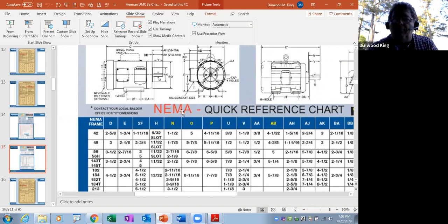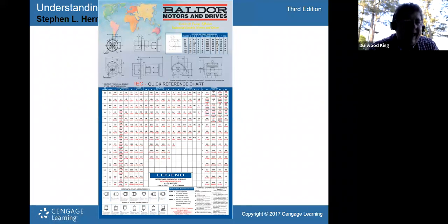But if you got motors that come from overseas, let's back up and look. Let me go back to full screen. Now, if I back up one, it says IEC. So the IEC is the International Electrotechnical Commission, and they're based out of, is it the Netherlands or somewhere over there in Europe? It's European. I forget what it is, and it may be even Belgium. It may be Brussels or somewhere over there, but it's Europe. So the IEC are metric. They're metric designations. So any equipment you get from overseas is going to have IEC rated motors, and the frame sizes and all that stuff. It's a whole different rating system, but it's still dimensional.